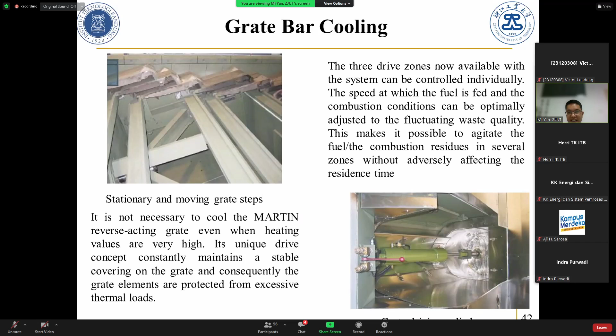And grate bar cooling: the company has both an air-cooled and water-cooled version of the grate technology. The designs are interchangeable. What does interchangeable mean? It means you use their product, their machine, and they can change your cooling style. So at the beginning you install an air cool grate, but 5 or 10 years later the heat value increases, meaning the feed of your waste becomes better. Then they can change the grate piece to water cool. So it's very good, though of course the cost is higher.